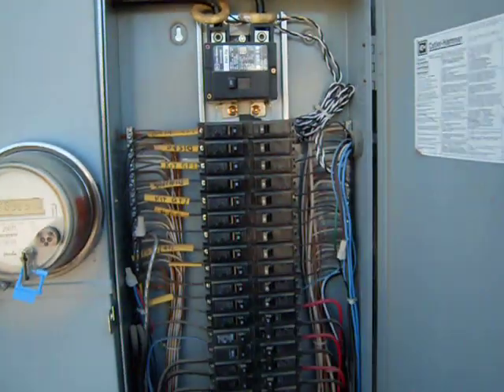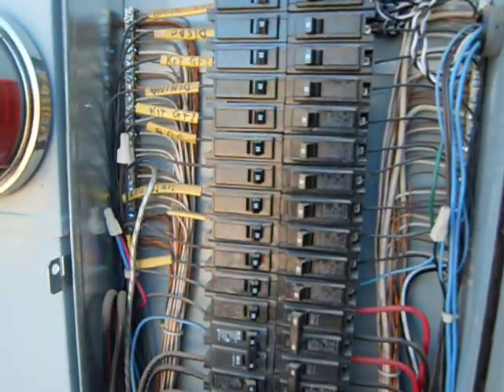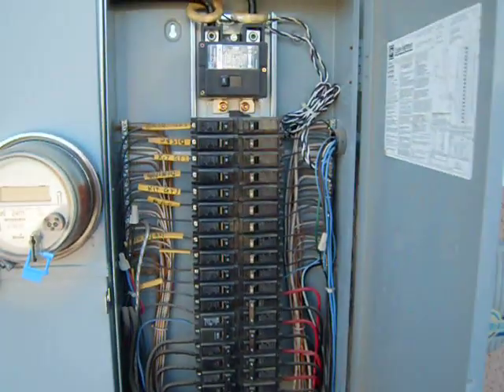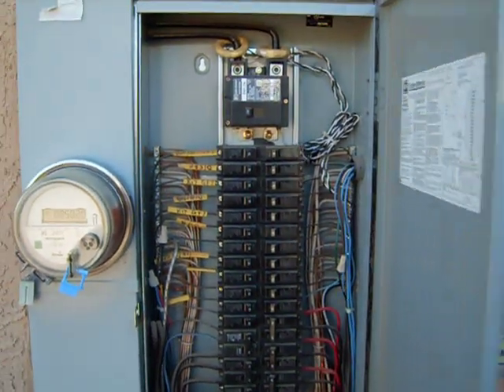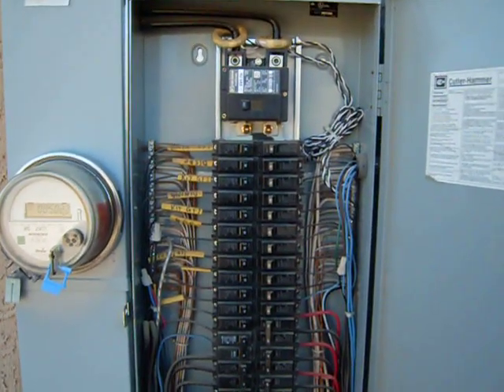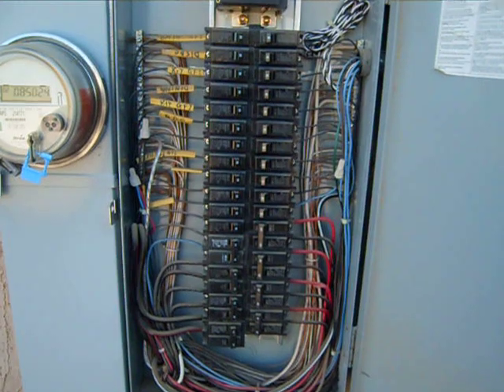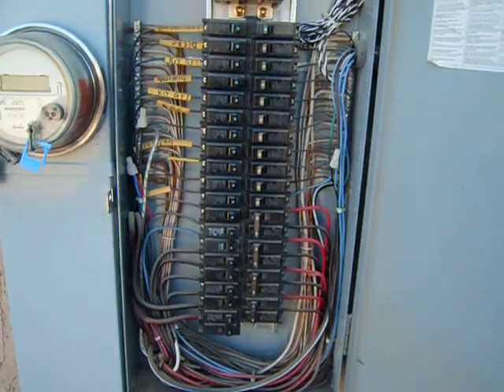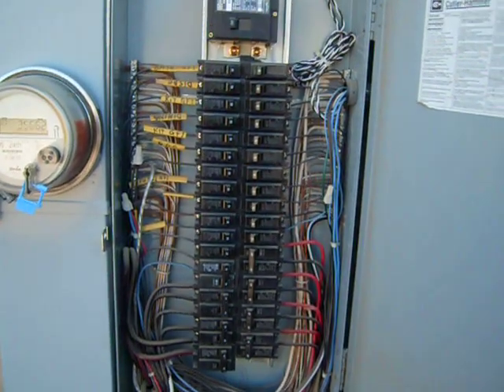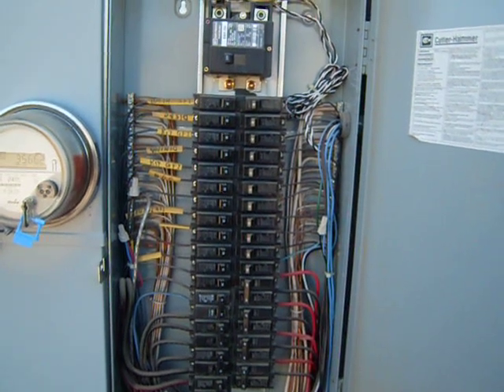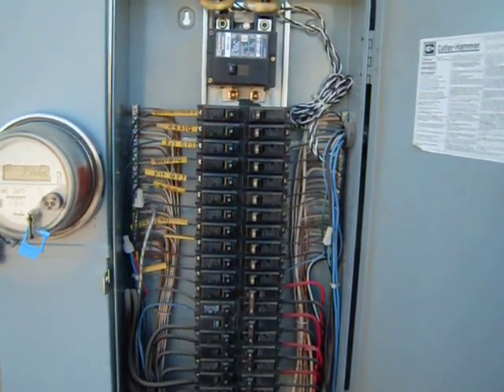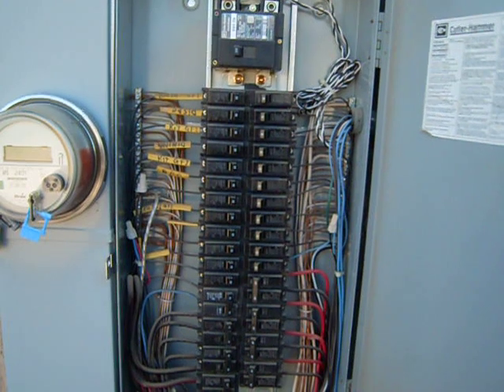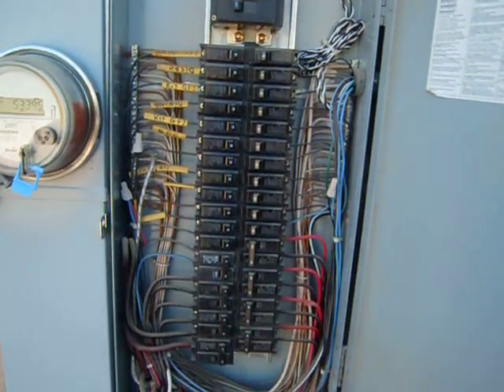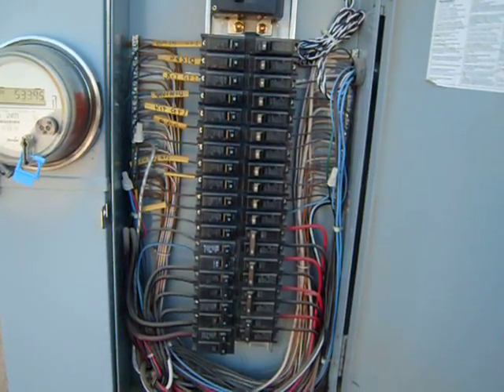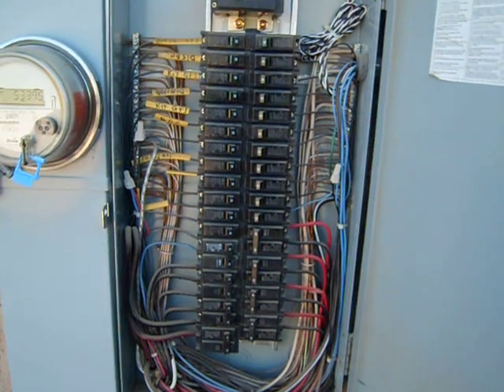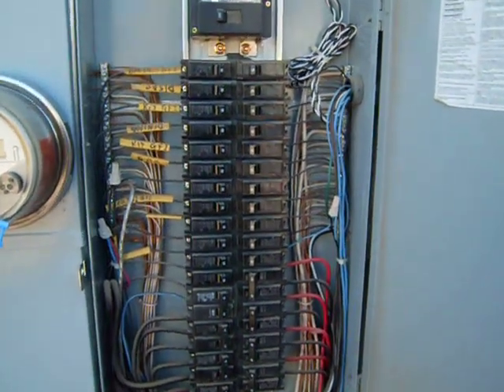Okay, I'm going to take my cover off here. I don't know if you noticed on my panel cover that I had it labeled. One of the things you want to make sure you know is what all your circuit breakers feed. So if you don't have a properly labeled panel, go ahead and take some time. Get one person, maybe on a telephone, over by the main panel, another person inside the house, and go ahead and go through and check and identify all the circuits and get it labeled. If you ever have any problems, you're going to want to know what circuit breaker to turn off.